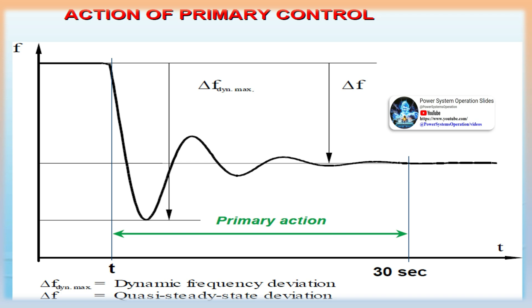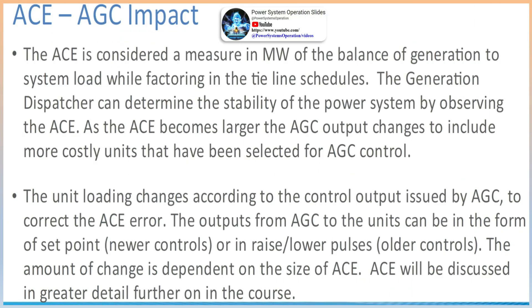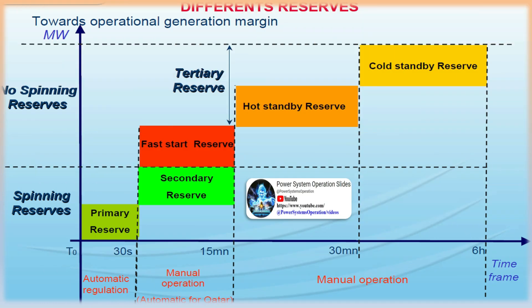With a low ACE deviation, no action will take place. As the ACE increases, different modes of operation occur as follows. Normal AGC response: once outside the dead band, normal regulation will send out raise or lower values equal to 90% of the value of ACE. Assist AGC response: if the ACE is large, then AGC will switch to assist and 105% of the value of ACE is requested. Emergency AGC response: if ACE is very high, the AGC will switch to emergency and 120% of the ACE value is sent to the AGC units. All units selected to AGC will respond in the emergency mode.